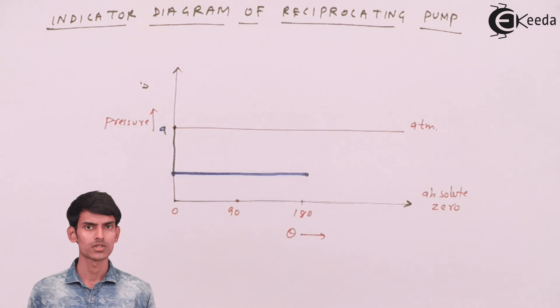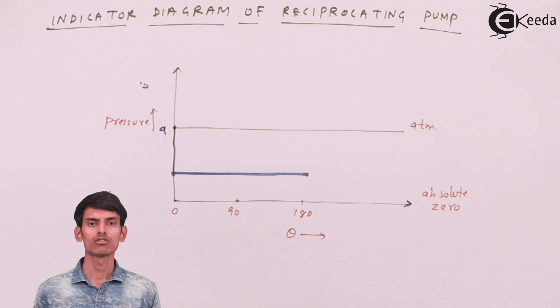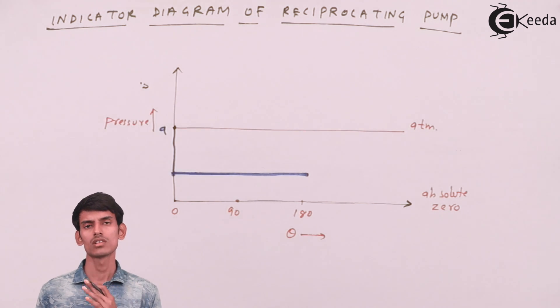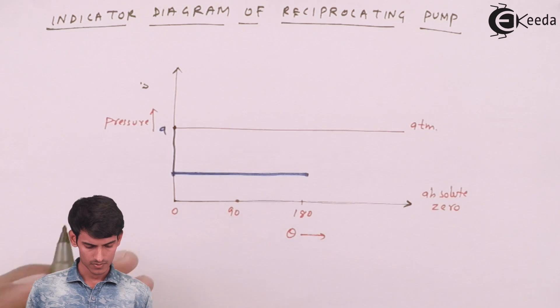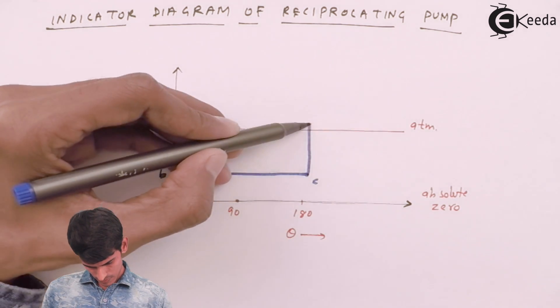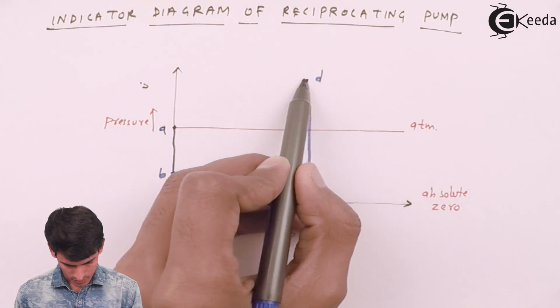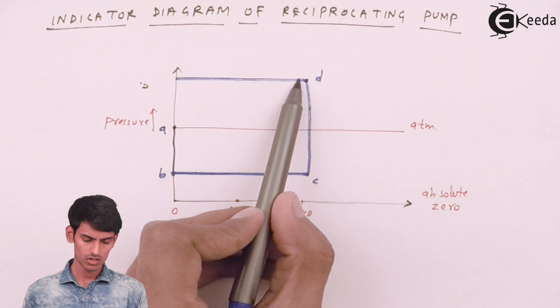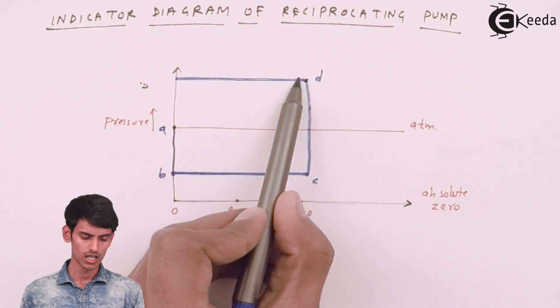At 180 degrees of crank angle the suction stroke ends — water has been sucked inside the cylinder. We'll assume the pressure instantaneously rises now, because after the vacuum has been created and water pulled inside, the pump must compress the water. The pressure rise is well above atmospheric. The pressure rises instantaneously to point D, and the delivery stroke begins — water is compressed and simultaneously delivered out of the pump.